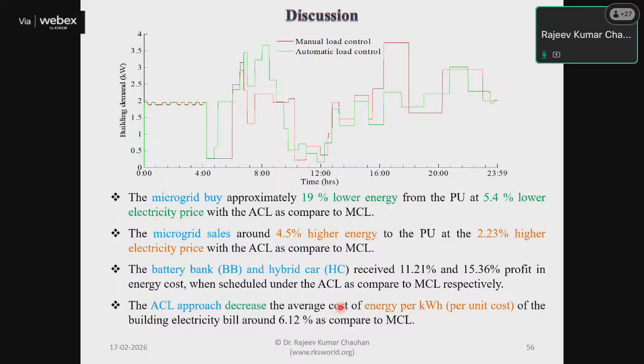Here we see the building demand, how it shifts from traditional mode to automatic. At night, only the grid is supplying, so the demand remains the same. But in the morning, with automatic load control, the demand has shifted from the traditional system's timing to a new time because prices were a little lower there. When generation is high and grid electricity prices are high, automatic control shifts the load from that time interval to here.